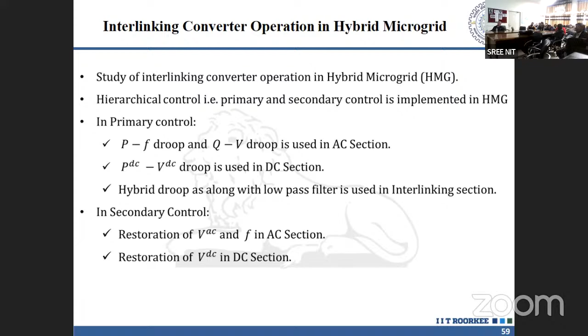For the DC to AC converter, we have the P-F droop. When the real power increases, the frequency will fall down, and Kp here is the slope of this line. So the frequency F equals F0 minus Kp times (PAC minus P0AC), where P0AC is the reference and PAC is the value at any point. This defines the droop.